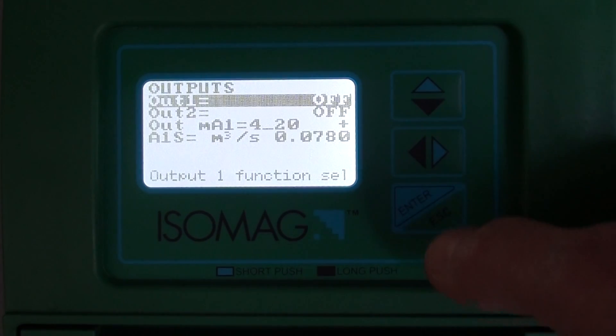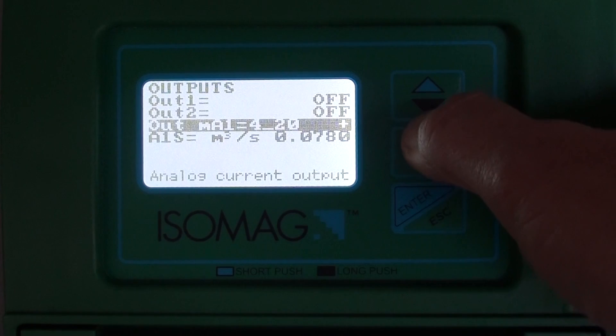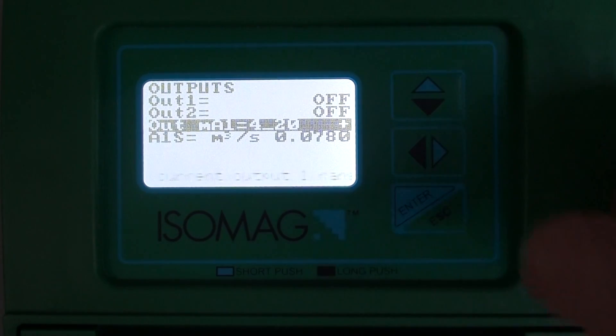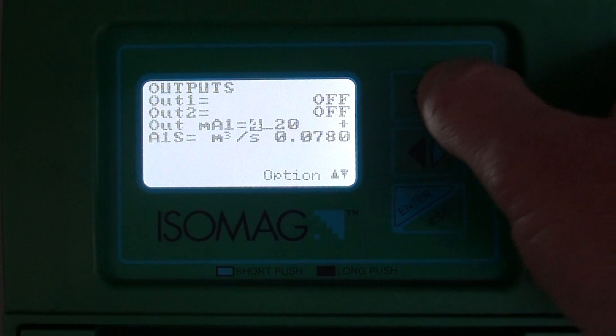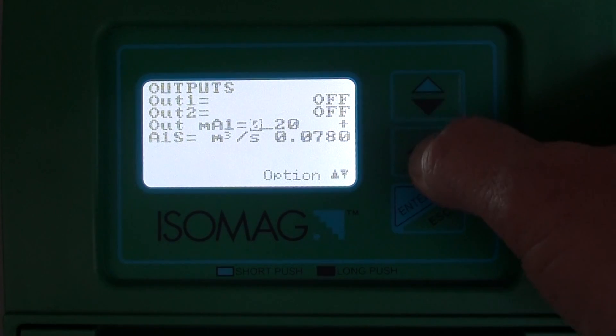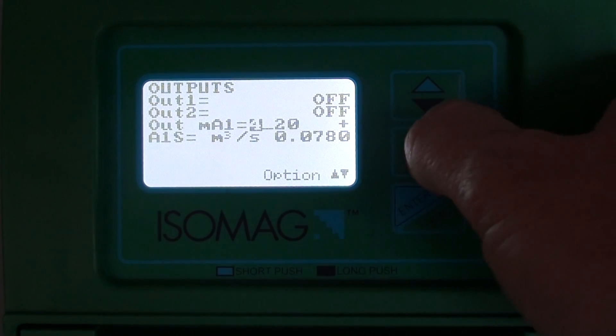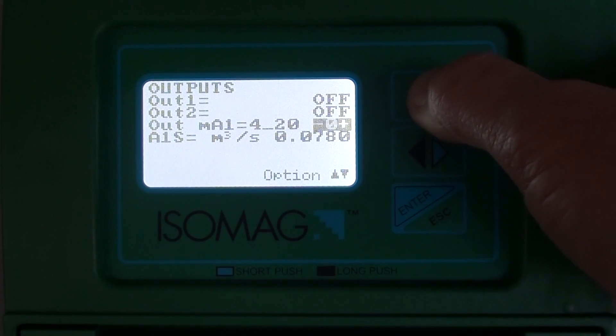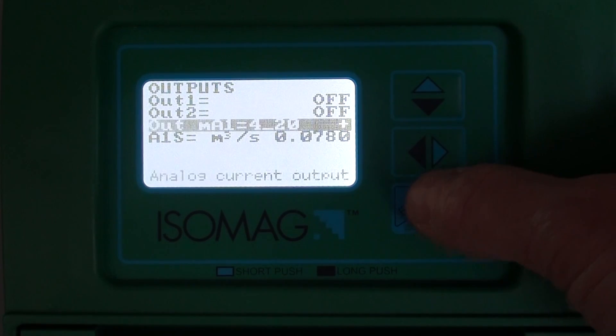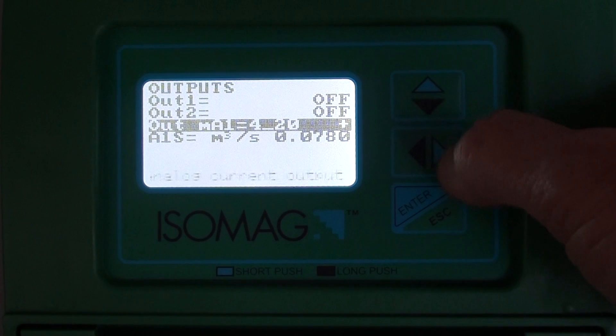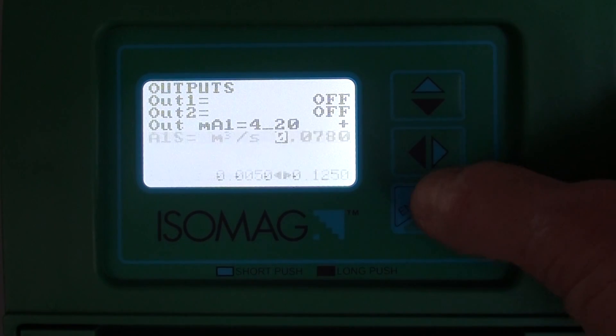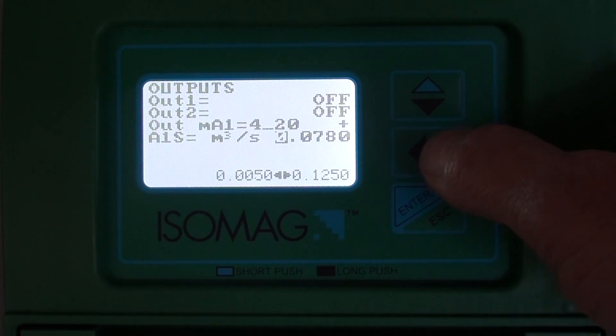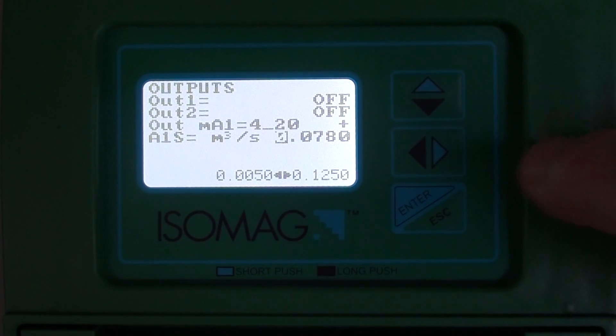Then we can go to the outputs menu and select how we want the 4-20 to work. We can select whether we want to start from 0 or 4 to 20 or 22, and in which direction we want the flow meter to work. Then we can select the relative flow velocity for the 20 milliamp.